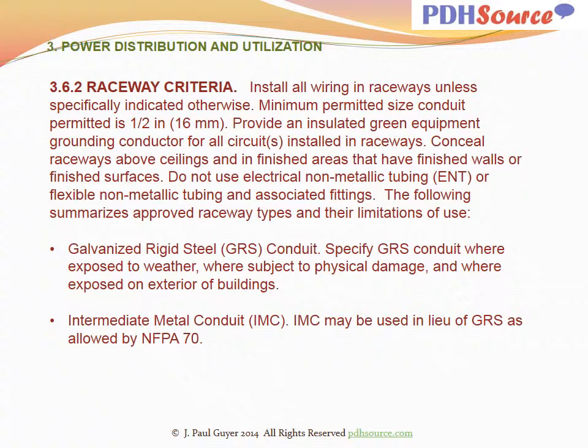With regard to raceway criteria, install all wiring in raceways unless specifically indicated otherwise. Minimum permitted size conduit is 1/2 inch. Provide an insulated green equipment grounding conductor for all circuits installed in raceways. Conceal raceways above ceilings and in finished areas that have finished walls or finished surfaces. Do not use electrical non-metallic tubing, ENT, or flexible non-metallic tubing and associated fittings.